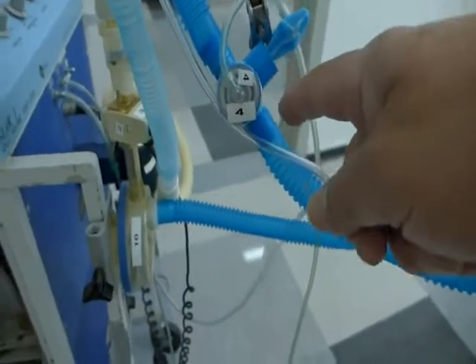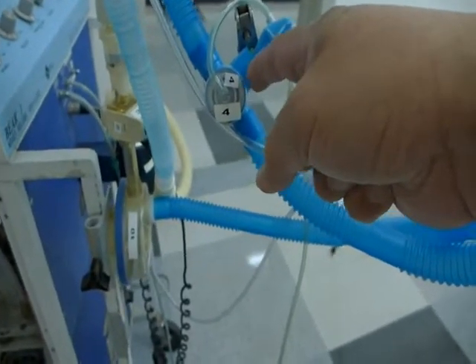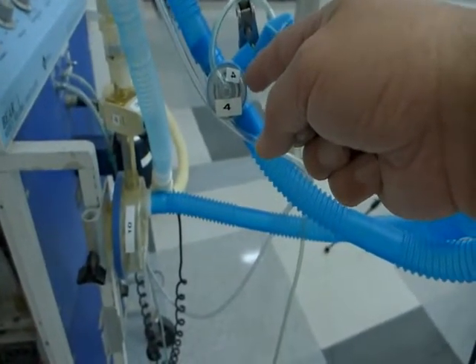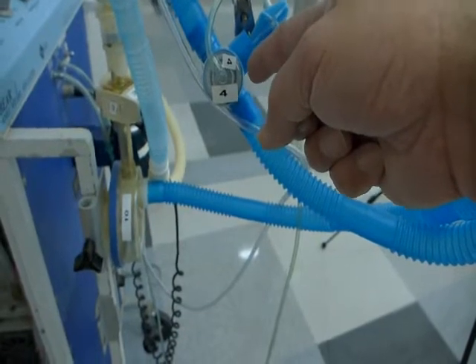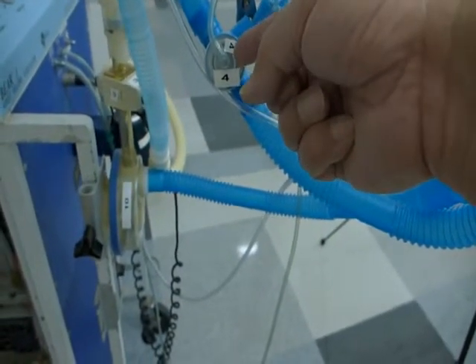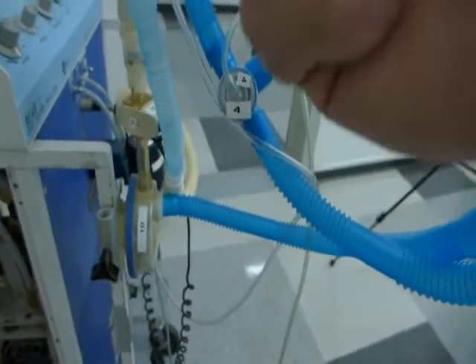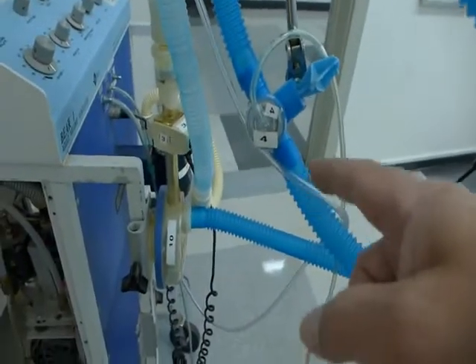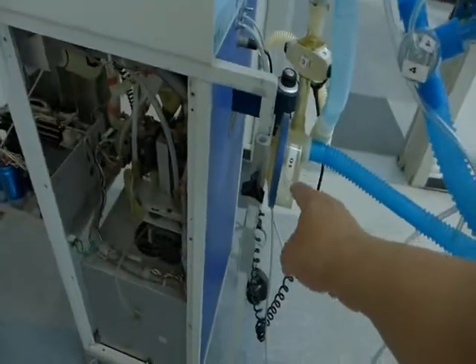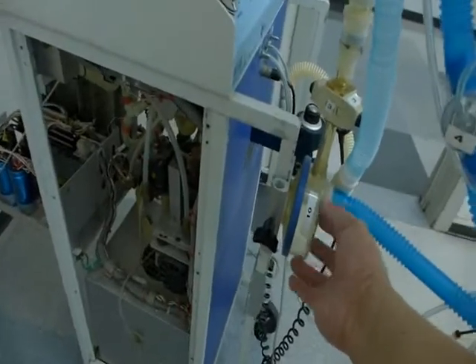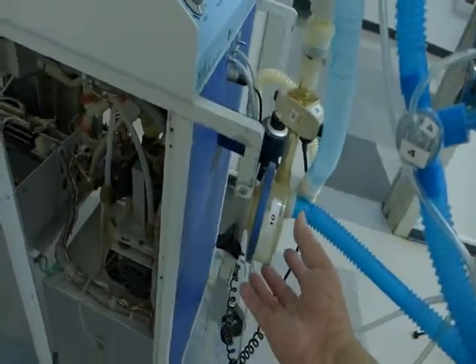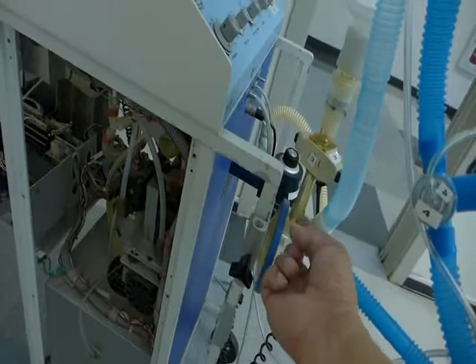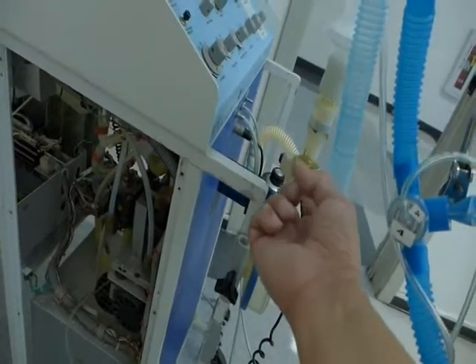Expiratory valve. What is its function? It will close during the patient's inhale, and when the patient exhales, it is open, allowing the gas from the patient to exhale. This is the water trap. Basically, it traps the moisture, and then the gas flows to the flow sensor.